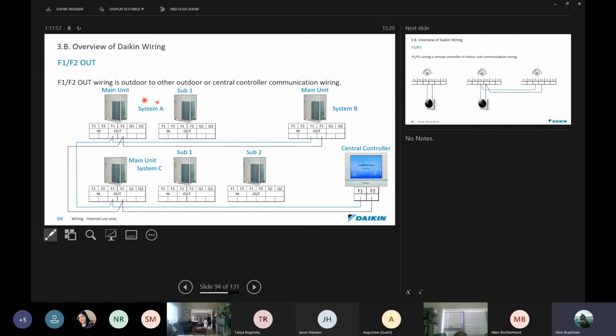Other wiring in the outdoor unit is the F1, F2 out. This is where I'm going to plug my laptop in when I come to commission. It's also where we plug centralized controllers in. In this configuration, only the master unit is looped if we're going to use a centralized controller. Remember, this unit is already connected to here by Q1, Q2, so the information will be transferred across. So there we have F1, F2 out from a single to a single slave unit, and then out to a unit with 3 condensers, and then onto the centralized controller.